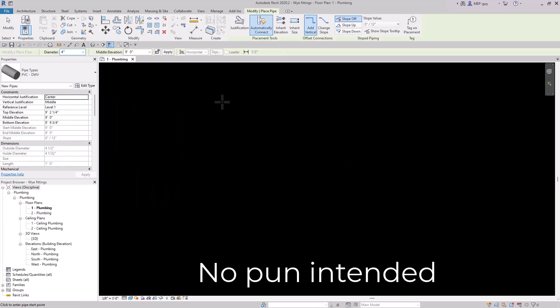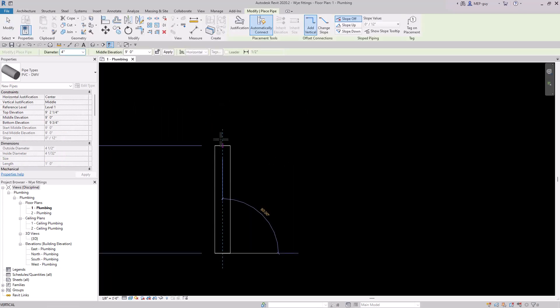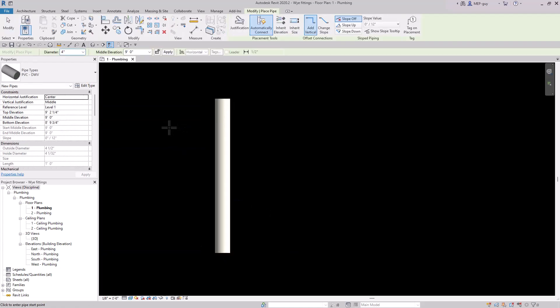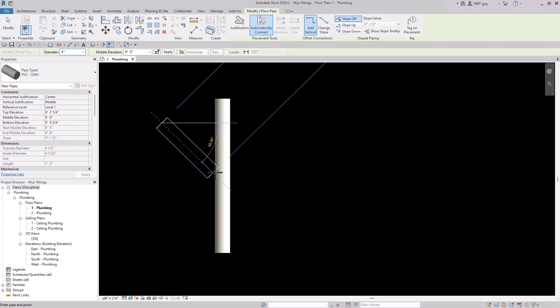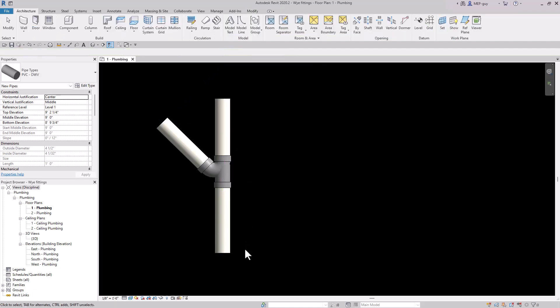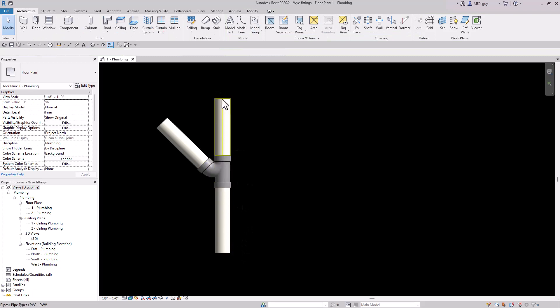Let's start drawing some pipe from the bottom up, and I'm going to 45 degree into this pipe at this location. Since we drew it from the bottom up, the flow direction is actually from the bottom to the top. Revit thinks the flow in this pipe is going this way, and that's why this little funky fitting happens right here.